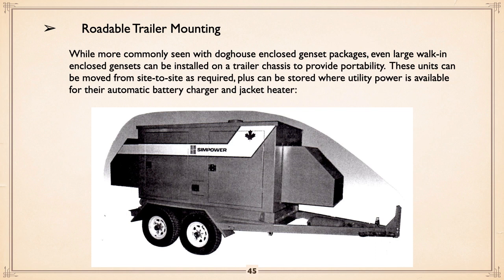Roadable units. Basically, they're usually a doghouse enclosure on a trailer. You're not so much worried about vandals because you can park this thing in a secure location. And they can be moved site to site. I remember one municipality, basically through their SCADA system, they were able to tell what the wet well levels were. So they would have somebody, a pickup truck or whatever with the genset on the back, go to the one that's got the highest level, closing in on overflow, pump that thing right down, and then go to the next one that's next highest and move themselves around. Bit of a pain, but it saves money. Also, you can store it where there's utility power, so the automatic battery charger and jacket heater are there.